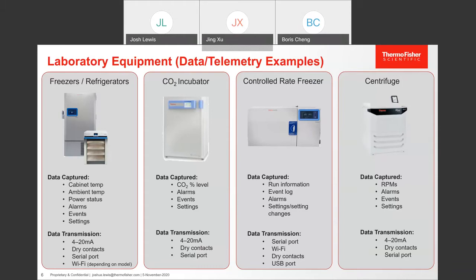Looking at a common theme across all this equipment, the 4 to 20 milliamp and dry contacts are pretty much a standard across the industry. Depending on the device it may be an option, but I can almost guarantee all laboratory equipment has one or the other available. The 4 to 20 and dry contacts are a primary connection point when connecting laboratory equipment with building management systems, or BMS, and also LIMS.